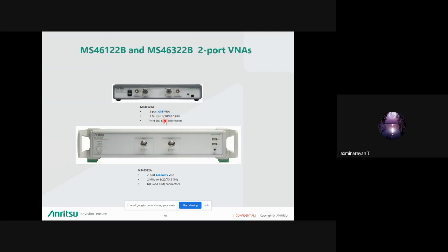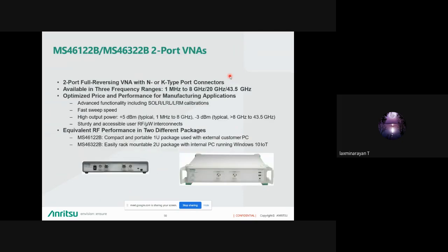So you need an external monitor for this one. For a 322B, you need an external monitor. For a 122B, we need to control from a PC or a laptop. For 2-port full reversing VNAs and a K-type connector, it will have K-type port connectors where it will be connected to the PC.